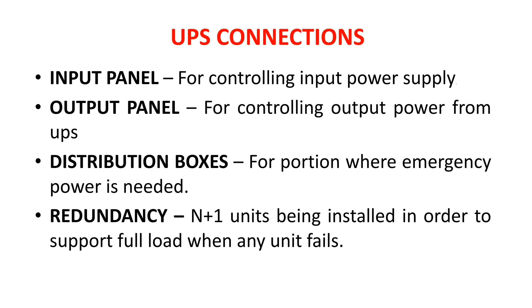Now in this slide you can see another word: redundancy. What is it? Redundancy is a connection of N plus 1, meaning connecting an extra UPS to N number of UPS so that the connected load can be handled easily when any of the UPS fails. Like if we have a requirement of a 20 kVA UPS, we can connect 20 plus 20, or two numbers of 20 kVA UPS. If any of them fails, the other one will be able to handle the complete load.